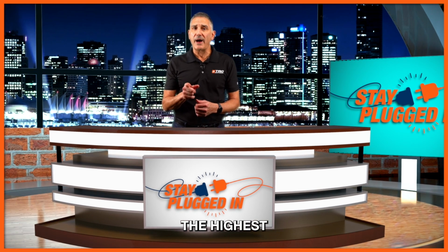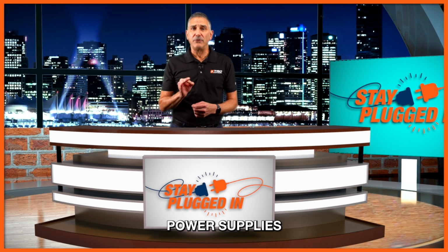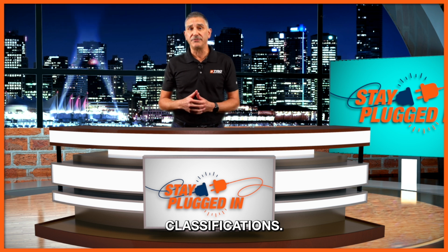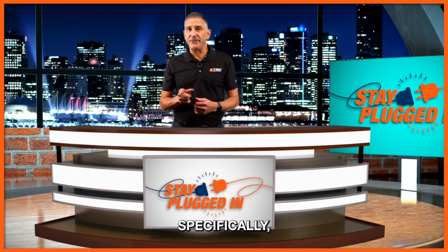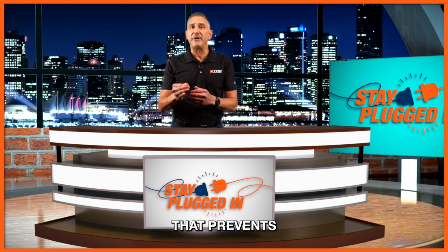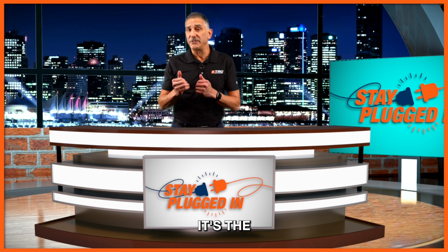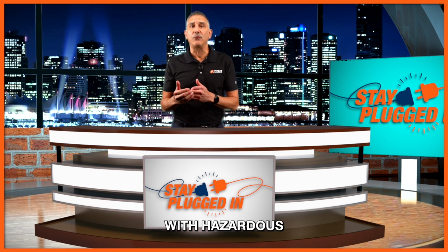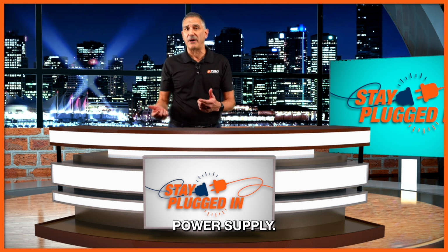Now, to ensure the highest levels of safety, power supplies being used in medical applications need to be compliant with the various parameters and classifications. Specifically, the means of protection refers to the protection isolation that prevents the equipment operator or the patient from coming into direct contact with hazardous voltages of the power supply.